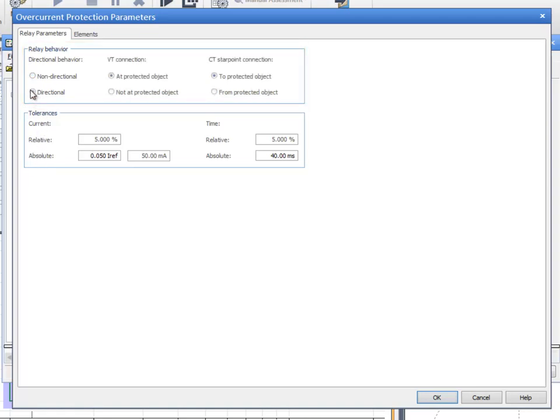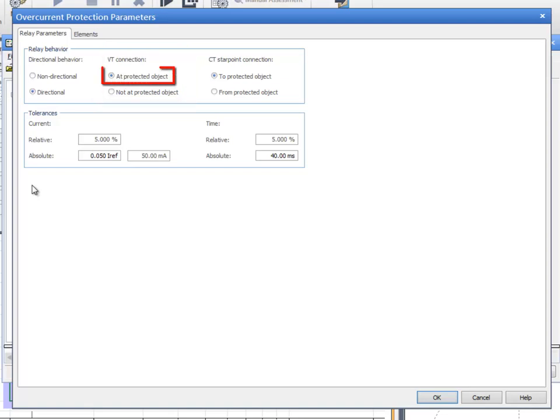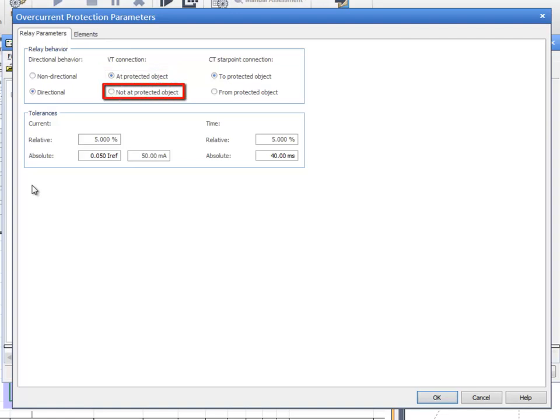The VT can be installed before or after the circuit breaker. Select At Protected Object when the VT is installed after the circuit breaker. Select Not At Protected Object when the VT is installed before the circuit breaker.